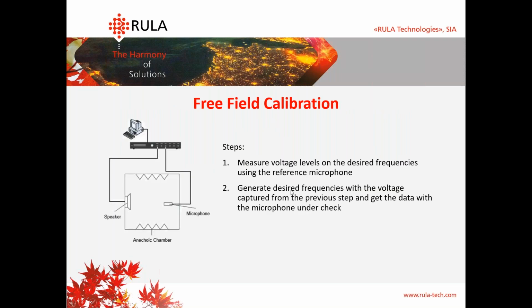And finally, let's talk about free field calibration. Here you see we have our controller, an anechoic chamber with a speaker inside, and a microphone. On our first step, we measure voltage levels on the desired frequencies using the reference microphone. So we get, I can say, ideal values for these frequencies. After that, we change our microphone to the microphone under check, and we start to generate all these frequencies with the voltage values captured from the previous step.